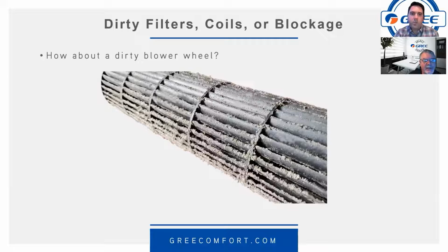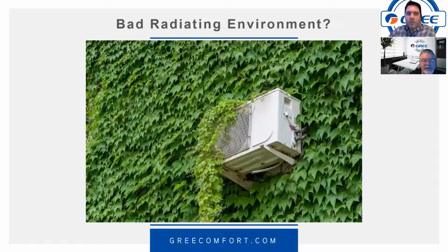Yes. But dirty filters, dirty coils, dirty blower wheel, I've seen this a lot. The filter's clean, the coil appears to be clean. Take your flashlight and shine it up in through the louver, and you'll see that the blower wheel has some buildup on it. It could be pet hair, it could be a number of different things, and probably particularly in the southern, more humid climates, I bet. There are some things you can do to mitigate a situation like that, UV lights and some other things. But that's an important thing to check, and fairly easy to clean.